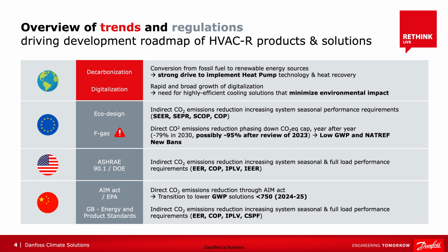The other thing that is changing the market is the indirect CO2 emissions driven by ASHRAE 90.1 and the Department of Energy for changing of seasonal and full load efficiency. So full load like EER, chiller efficiency, COP, part load efficiency like IPLV, etc. The other thing that we're seeing is a big change with the Infrastructure Acts, the AIM Act and the EPA Act, driving CO2 emissions through changing an HFC phase down through the AIM Act as well, moving to lower GWP solutions below 750 and HFC phase down requirements.